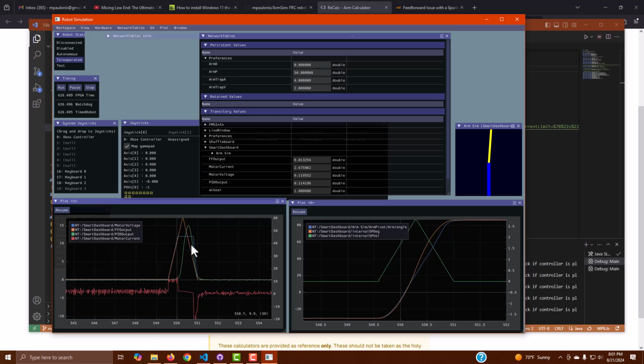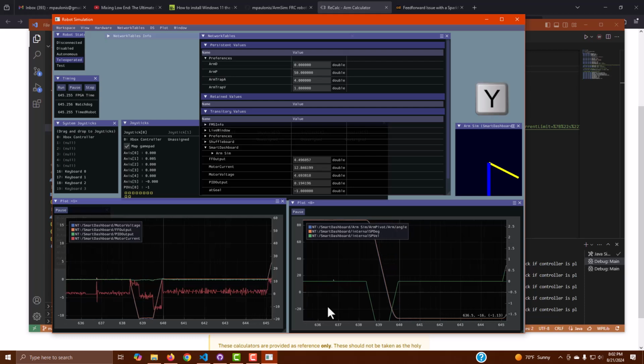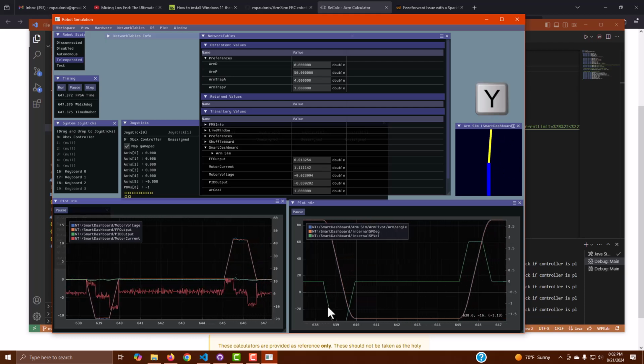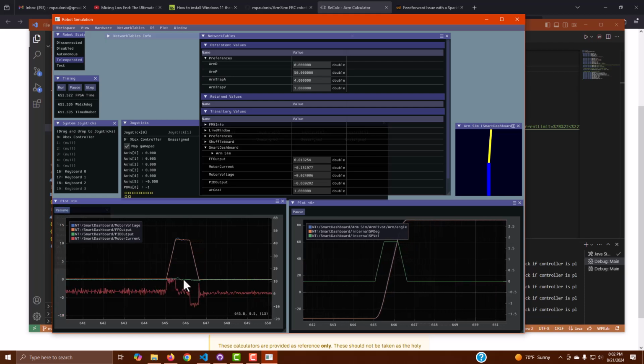You could also look and see what happens if your feed forward parameters are wrong. So we'll put this back to where it's feasible again. Let's drop it back down. Whoops, let's resume here. So we can see, and just to remind ourselves, we go back up and it looks like that. And our PID is doing very little because our feed forward is so good.